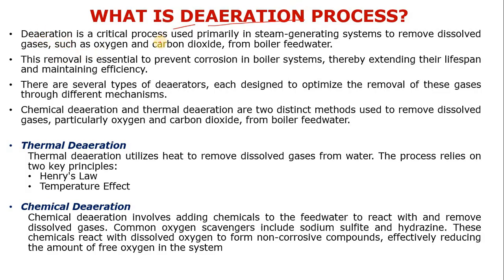De-aeration is a critical process primarily used in the steam generating system — it is part of the boiler package. We use the de-aeration process to remove dissolved gases, namely oxygen and carbon dioxide, from the boiler feed water. This removal is essential to prevent corrosion in the boiler system.